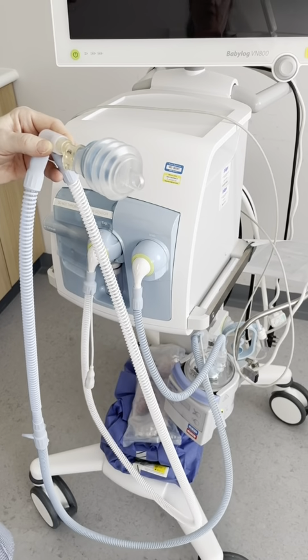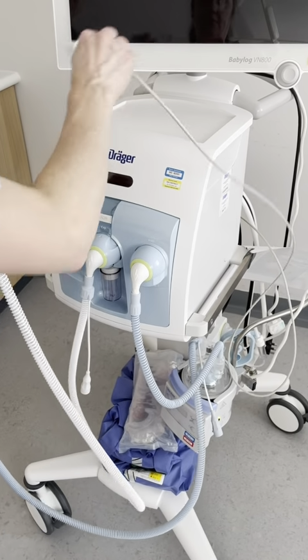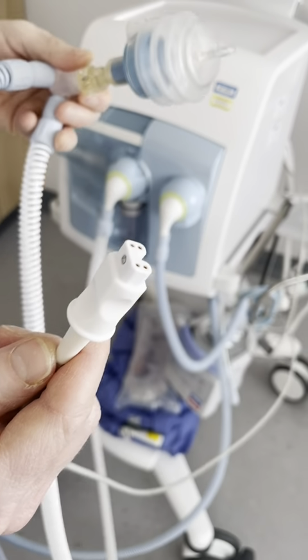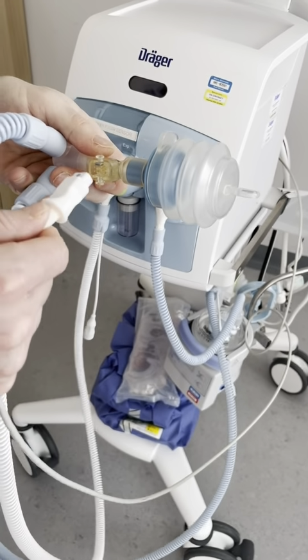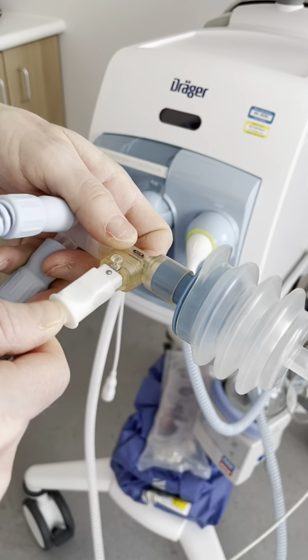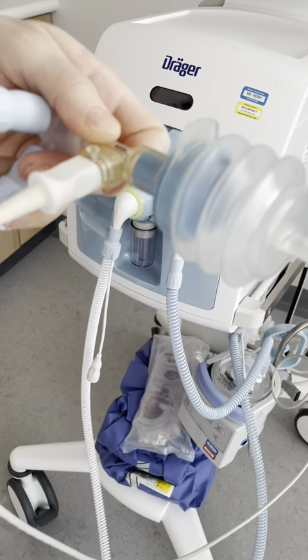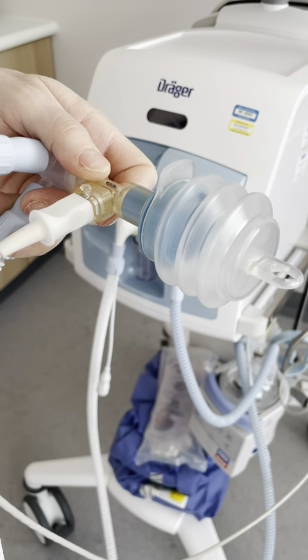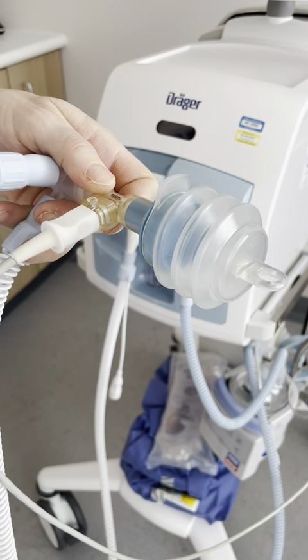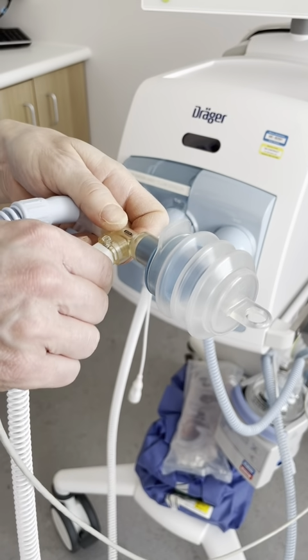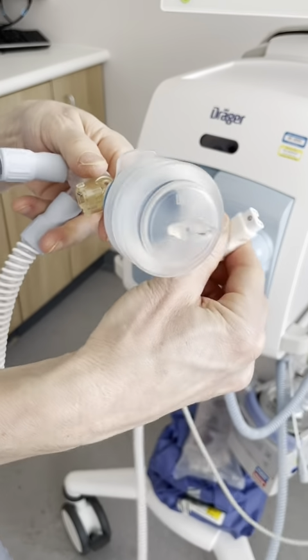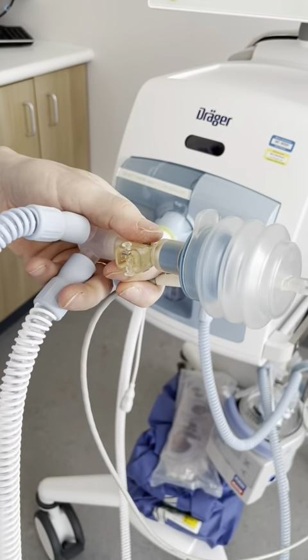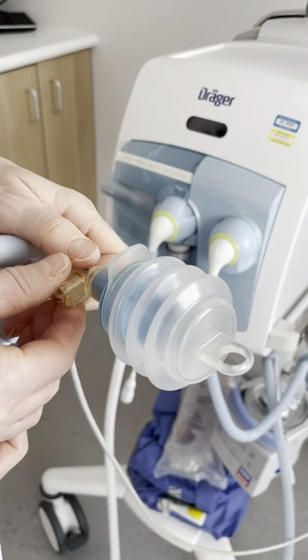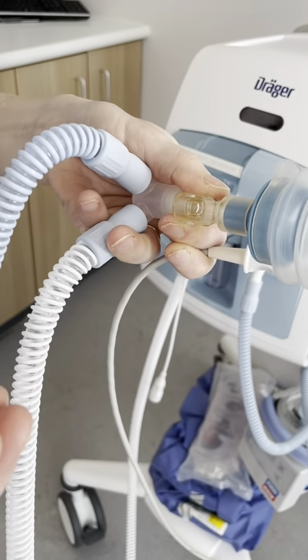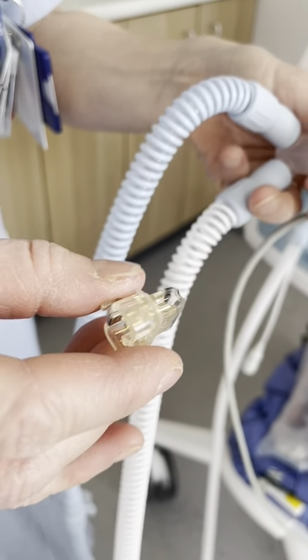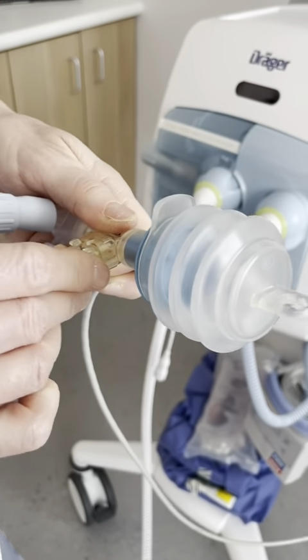The airway sensor cord will already be plugged into the back of the ventilator. The other end needs to be inserted into the plastic airway housing. This needs to be done gently as the sensor is easily damaged. If the sensor does become damaged, do not throw the plastic sensor housing away, but you can remove the sensor insert. This is done by gently squeezing the sides and replacing with a new sensor insert.